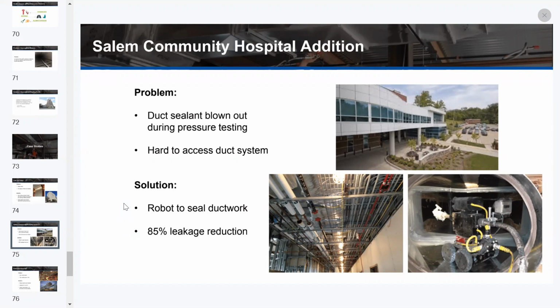Contractor had to turn that building over, but could not until the leakage was within specification. Lower left picture, you can barely make out the ductwork due to the racking system. It was all 20-foot sections built offsite and installed in 20-foot sections. It just made accessing the system to repair it really challenging. Solution was a robot, which you can see in that lower right picture, and a spray applied sealant to seal the ductwork on the inside. The result achieved about an 85% leakage reduction and allowed the contractor to turn over the building on schedule. And I can tell you that particular contractor, I think, would have given us his firstborn child.